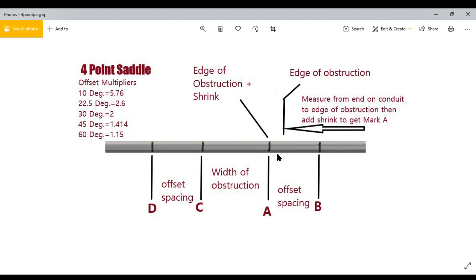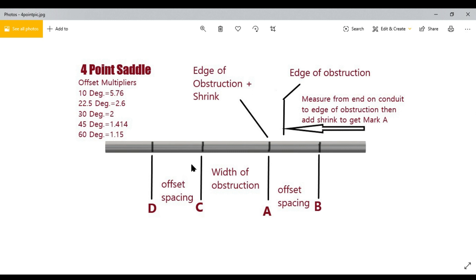After that, measure out your spacing to your first offset and mark it — that's Mark B. Then from Mark A, measure the width of your obstruction and mark that as Point C, which is your second offset. Finally, add the same offset spacing from C to get Point D. That's it — you've laid it out.